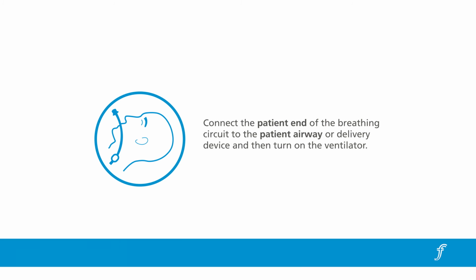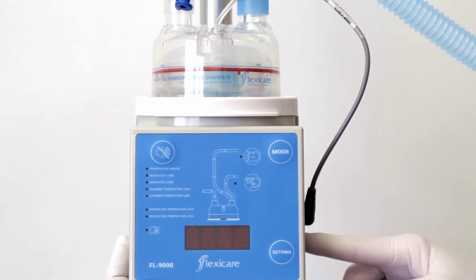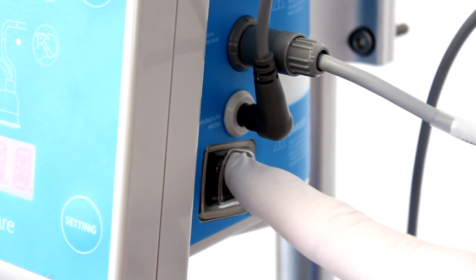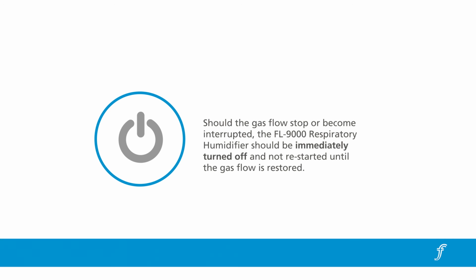Connect the patient end of the breathing circuit to the patient airway or delivery device and then turn on the ventilator. Only when the chamber contains water and the gas is flowing through the breathing system should the FL9000 be turned on and warming and the humidification of the respiratory gases begin. Please note, should the gas flow stop or become interrupted, the FL9000 respiratory humidifier should be immediately turned off and not restarted until the gas flow is restored.